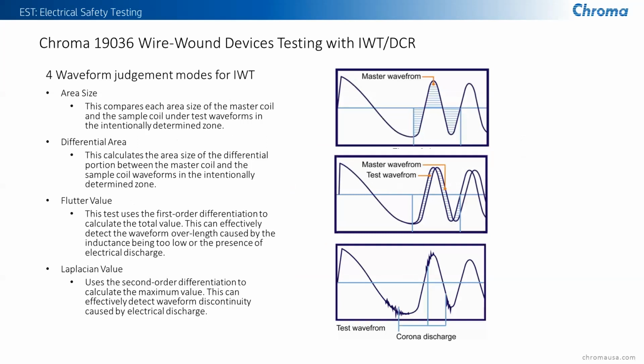One is the area size, which determines possibly the DC resistance of the wire, but it also can tell us if there are any shorted turns or any difference in the windings themselves that might cause an imbalance or difference of the inductance of the wires. Differential area, this is looking at possibly a variation that would be related to, again, possibly shorted turns, but it also could be an indication of the actual inductance of the coils.